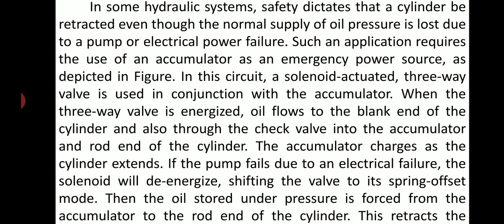In some hydraulic systems, safety dictates that a cylinder be retracted even though the normal supply of oil pressure is lost due to a pump or electrical power failure. Such an application requires the use of an accumulator as an emergency power source as depicted in the figure. In this circuit, a solenoid actuated three-way valve is used in conjunction with the accumulator.